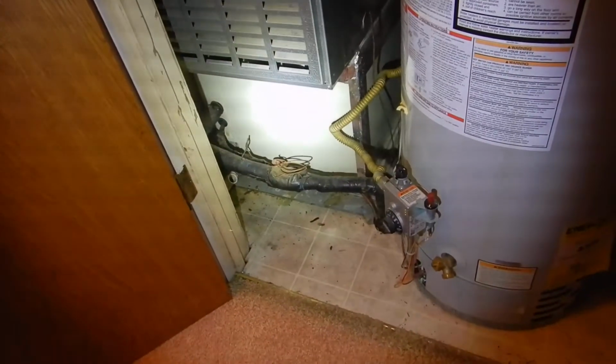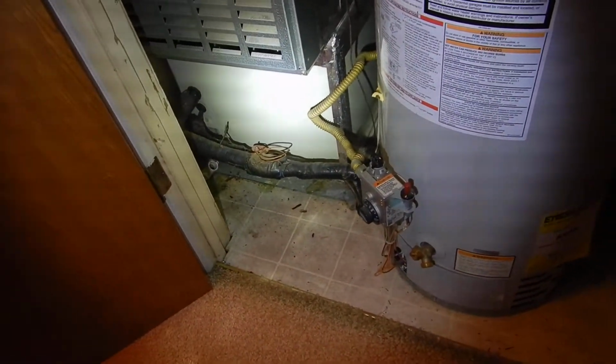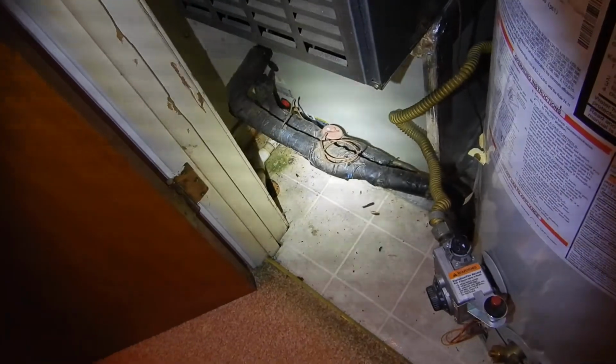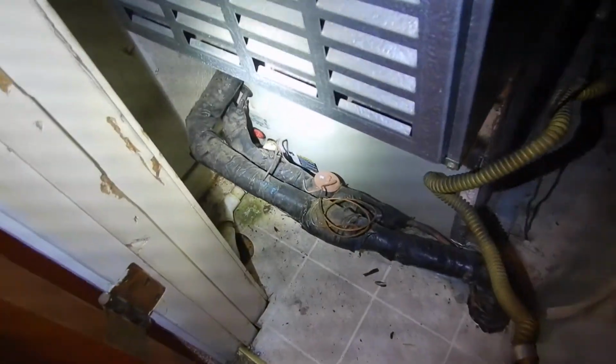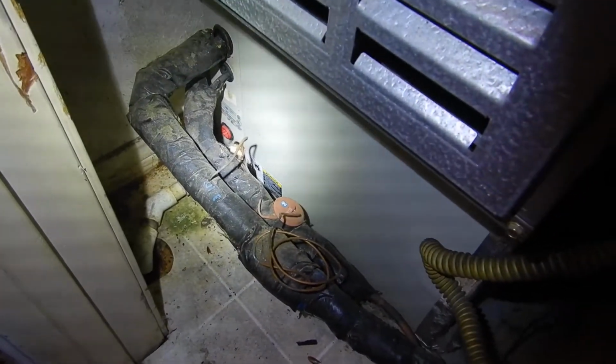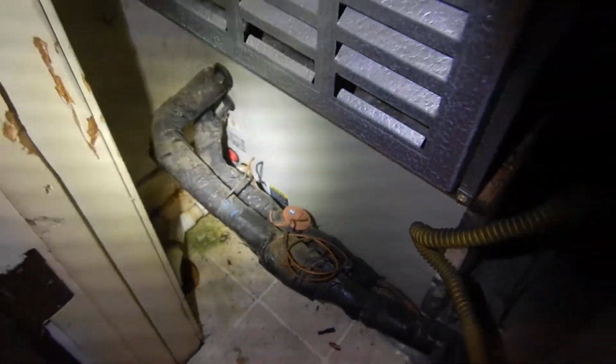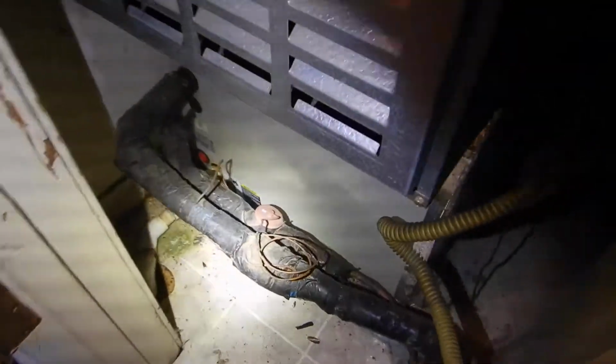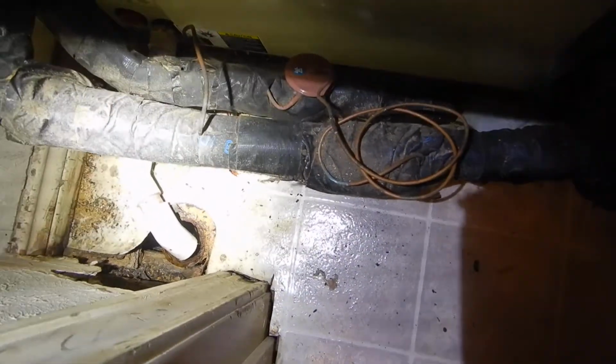So coming on down, these are our evaporator coils. And this insulation, unlike the condensing unit video you're about to see, the insulation is okay on these down here. But what we do not have is a secondary drain. We do not have a safety switch. Our primary drain does not have a P-trap, it's not insulated, and it's also clogged. This is draining right into the crawl space right now. That drain pipe is clogged. It is not draining properly. So we got a clogged drain.